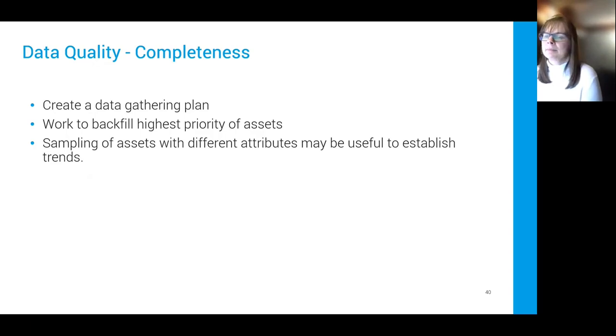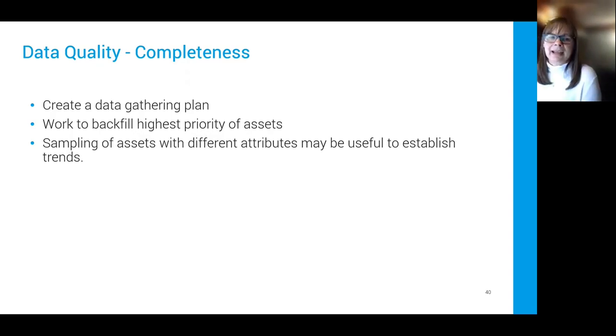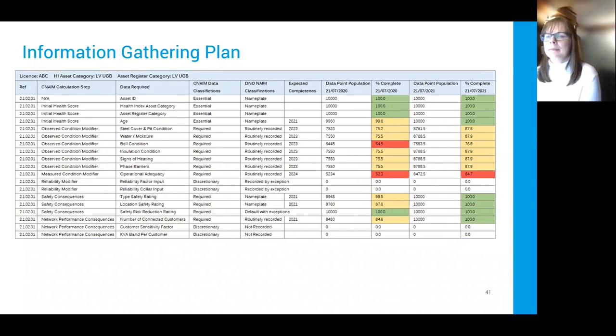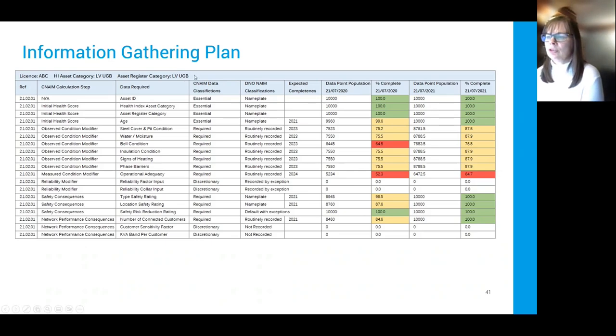On completeness: in the UK we've created information gathering plans — just setting out the stall of what information is going to be collected and when, and working towards that plan over time to backfill high-priority assets. In the PowerPoint pack there's an example information gathering plan from common methodology for LV underground cables, with different classifications: essential elements (things that make the model go), required elements (your condition points), and discretionary elements. Just adopting some terminology and making a plan, then working towards collecting that data.